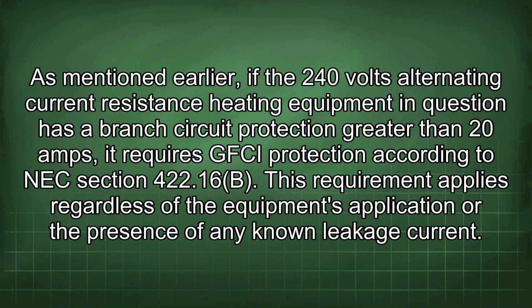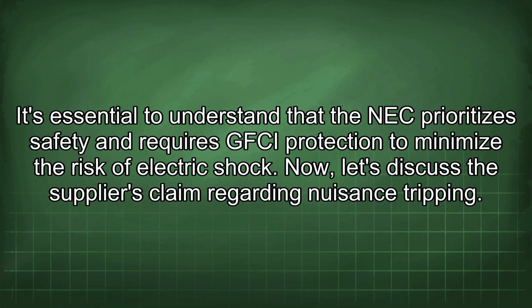As mentioned earlier, if the 240 volts alternating current resistance heating equipment in question has a branch circuit protection greater than 20 amps, it requires GFCI protection according to NEC section 422.16(b). This requirement applies regardless of the equipment's application or the presence of any known leakage current. It's essential to understand that the NEC prioritizes safety and requires GFCI protection to minimize the risk of electric shock.